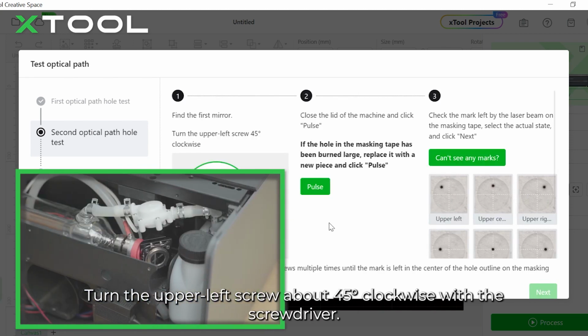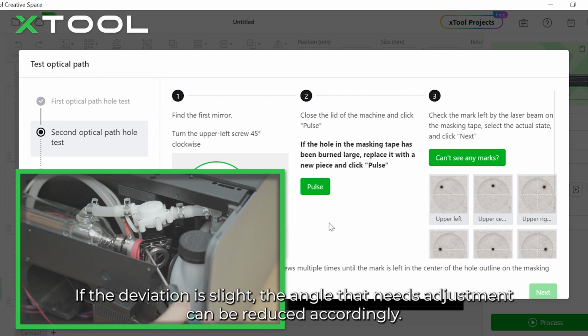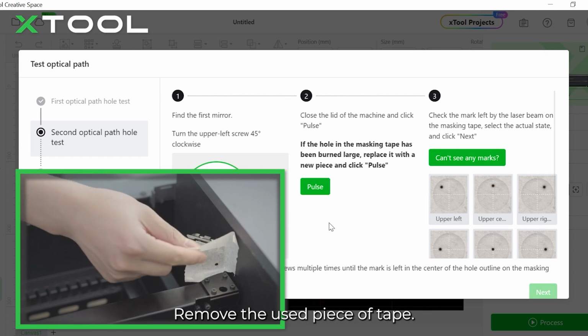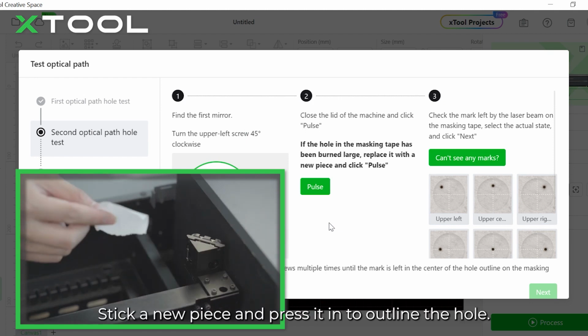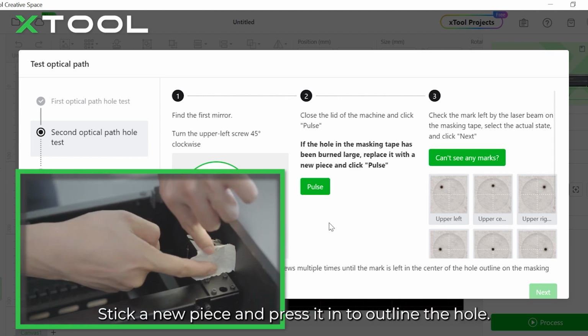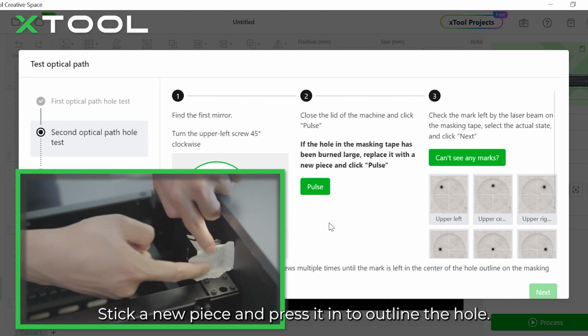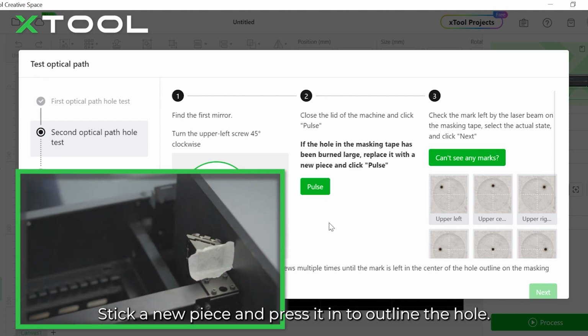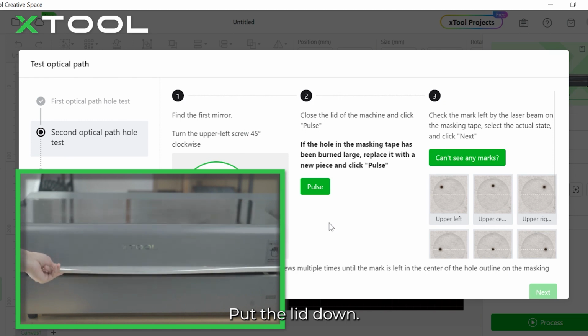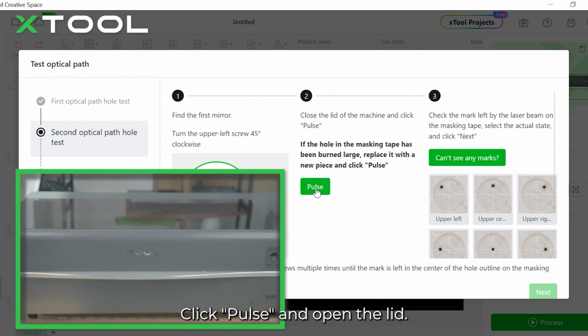Turn the upper left screw about 45 degrees clockwise with the screwdriver. If the deviation is slight, the angle that needs adjustment can be reduced accordingly. Remove the used piece of tape. Stick a new piece and press it in to outline the hole. Put the lid down. Click Pulse and open the lid.